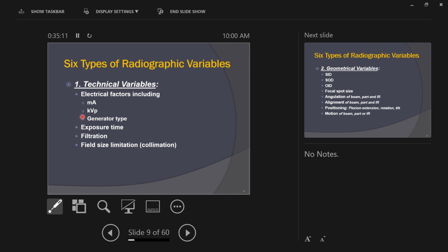That's why we pair exposure time with milliamperage, because they work directly with each other, and that's why we have a mAs number because of it, right? Most of the time when you're on an X-ray machine, you don't have to go, well, what's my mA, what's my exposure time, right? Here you do, right? Most of the time you just go, well, what's my mAs, and let me plug in an mAs number. So those two together, mA and exposure time, give you the total quantity of X-rays used in an exposure, okay?